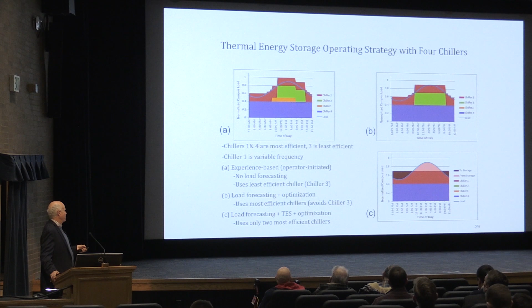You might say, okay, that was a nice little study, but did you save any money? Well, yes. Here you see three cases. What they were using was arguably an optimal policy called equal ratio chiller loading, which a lot of manufacturers recommend. But if we go in and analyze and model the system, doing either static or dynamic optimization, we can start reducing the cost, in this case from $23,600 to $21,800.